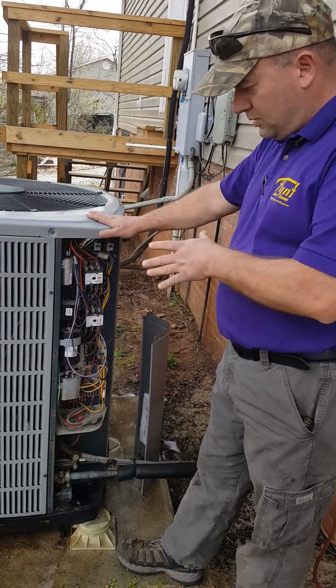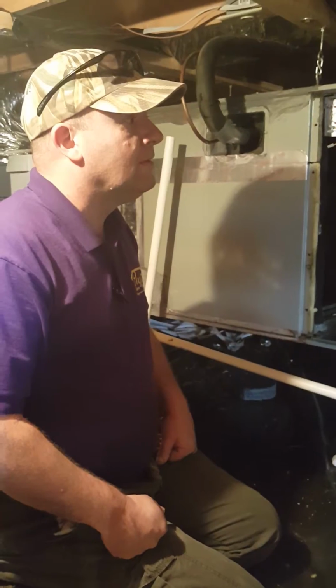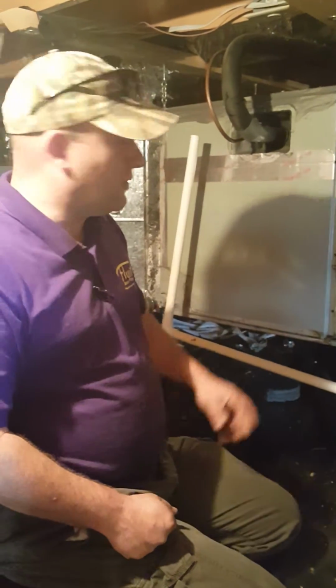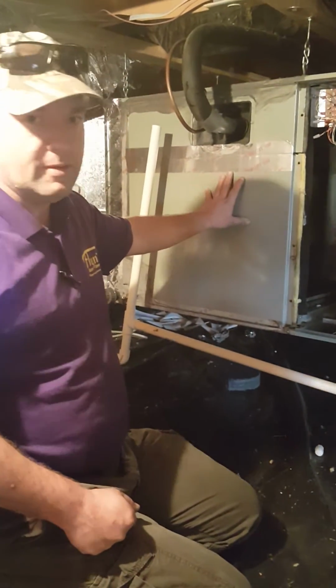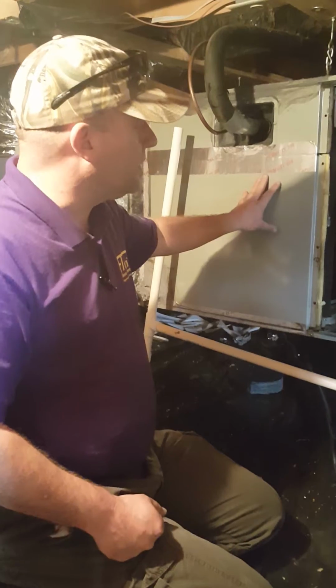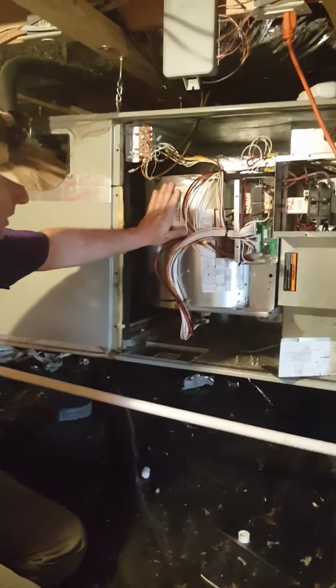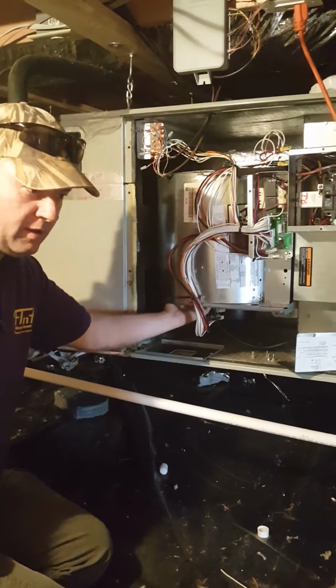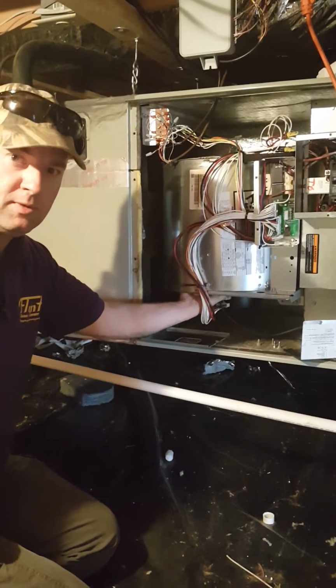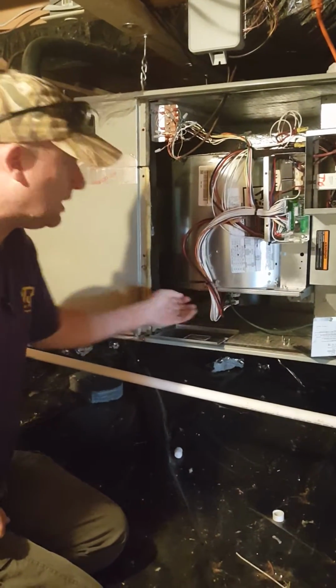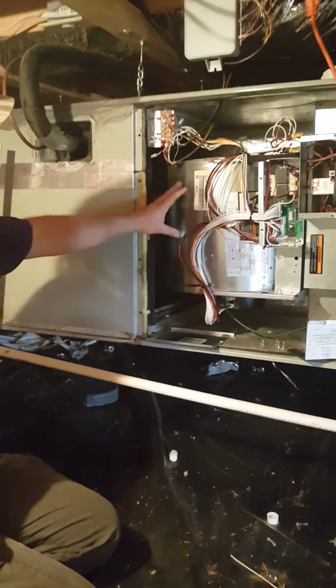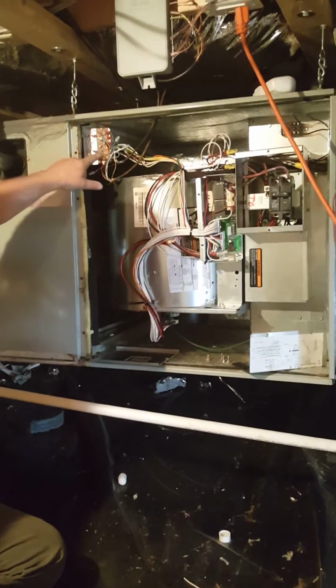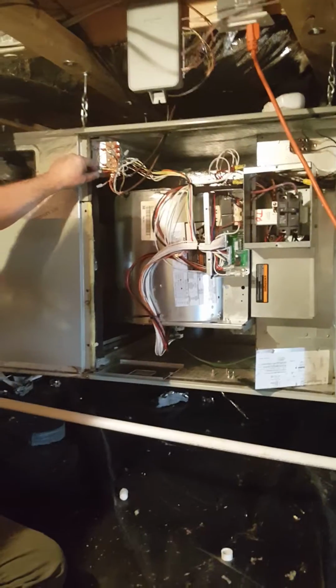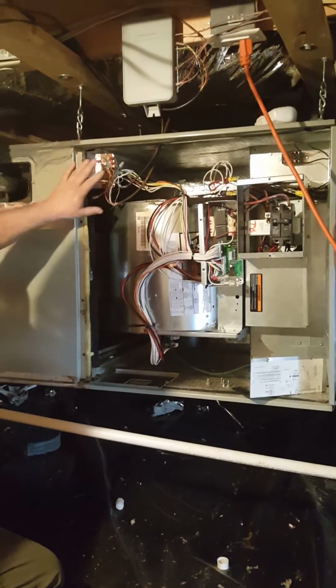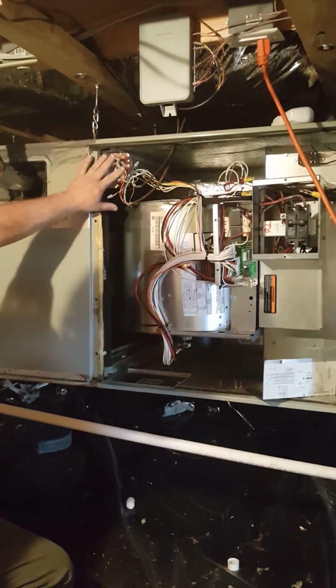We'll come back to this unit in just a minute. Alright, so we've got up underneath the house looking at the air handler unit. The things we're going to check under here are the blower cage and the blower wheel. We'll make sure dirt, debris, pieces of paper, or any kind of debris isn't caught up in that blower wheel, and clean that out. We're also going to check the thermostat connections, making sure all these wire nuts are tight, nothing's falling off, and all the connections are tight.